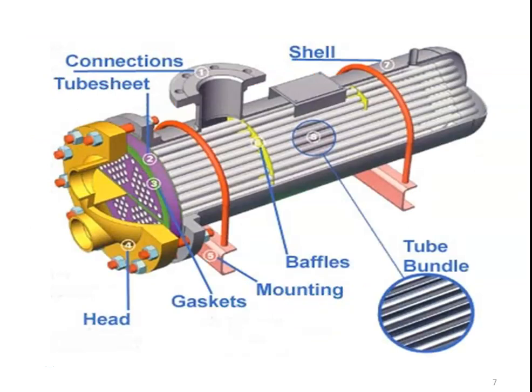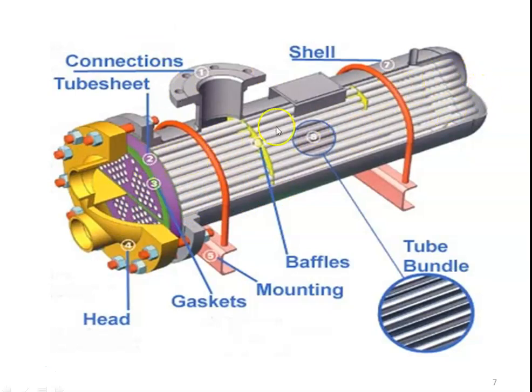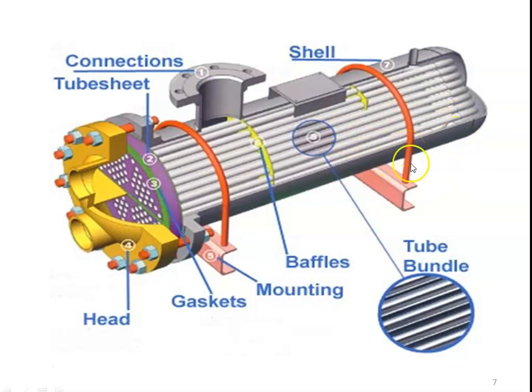This is an example of a shell and tube heat exchanger. We have a shell with the shell-side fluid entering on one side and leaving on the other. Inside the shell, we have a bundle of tubes running from left to right. The tube-side fluid enters, flows through the bottom tubes from left to right, takes a turn, flows back through the upper tubes, and leaves on the other side. This header collects the fluid. The inlet and outlet of the tube-side fluid and the inlet and outlet of the shell-side fluid are the four connections.